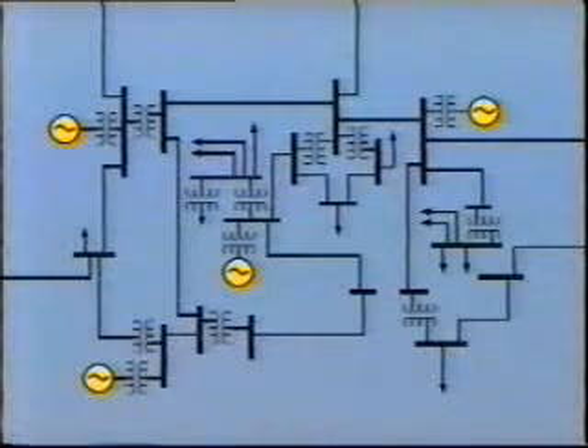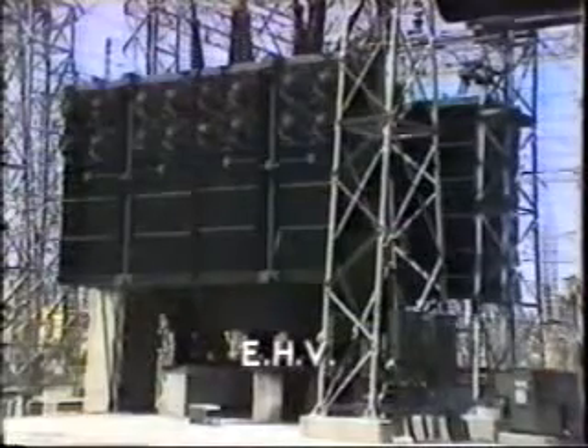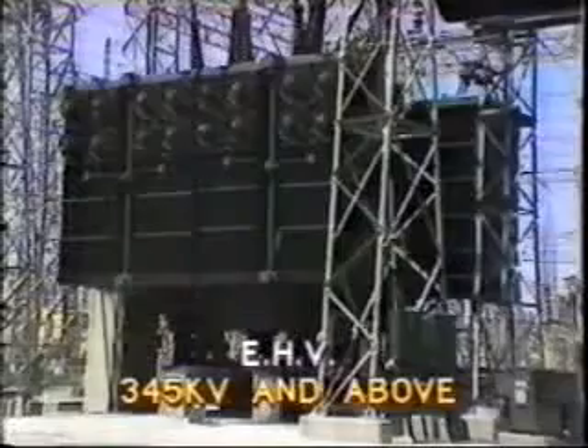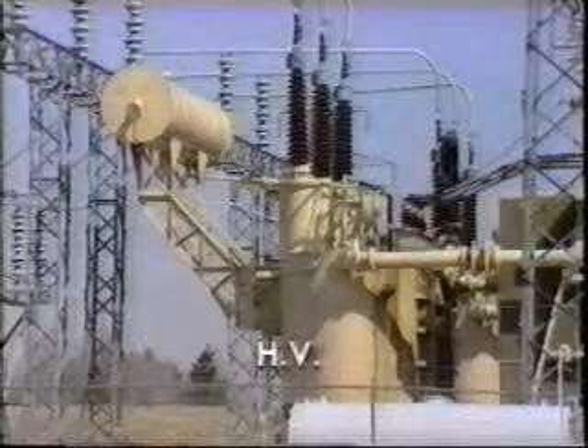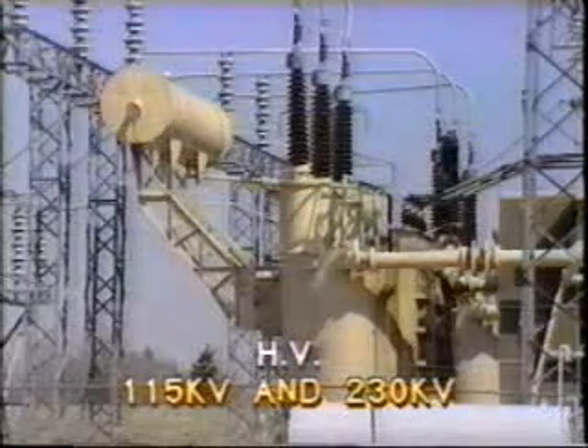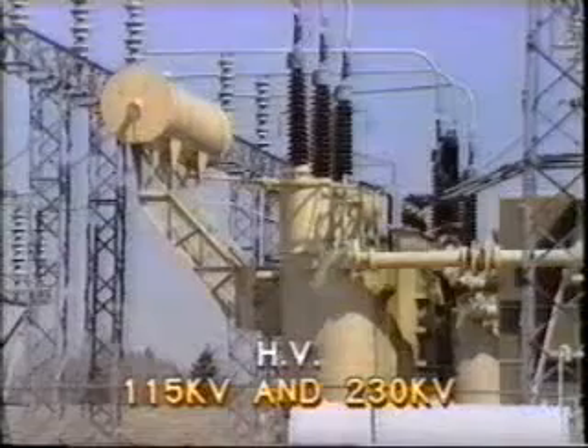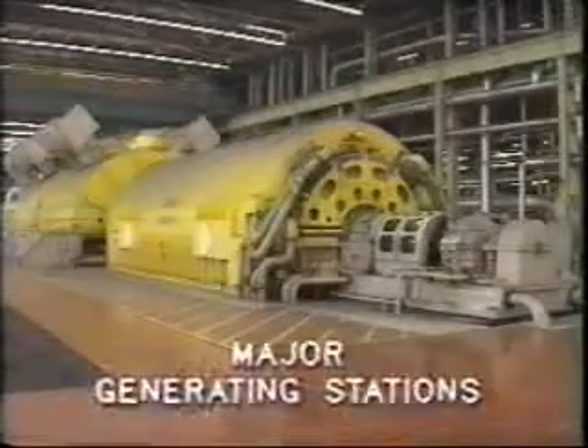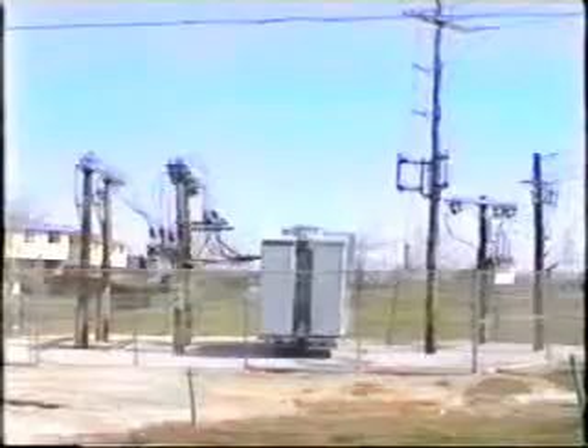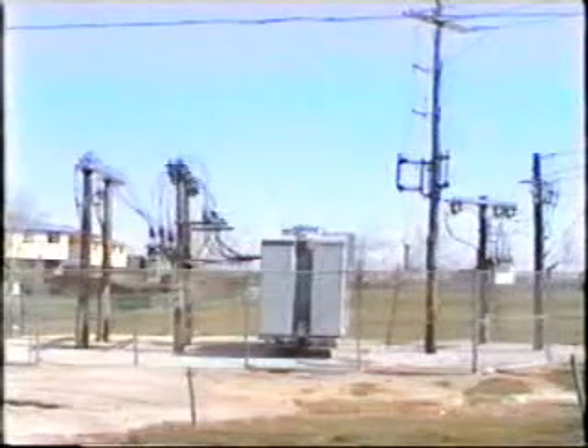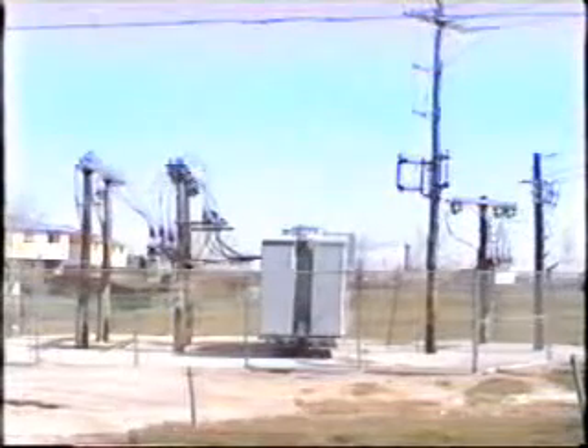As a general rule, most utilities find that they can adequately monitor the system by installing recording machines at every station in the extra high voltage range, that is 345 kV and above, and every other station in the high voltage range, such as 115 kV and 230 kV. This allows at least one end of each high voltage line to be monitored, every major generating station, and every station with interconnections to other systems. Normally, oscillographs are not located at the distribution substations except those installed to analyze special problems or to conduct research.